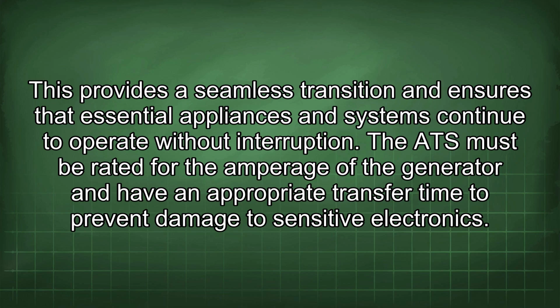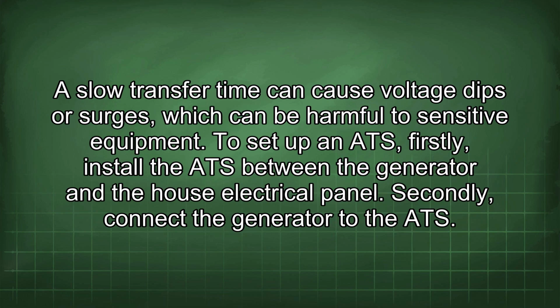The ATS must be rated for the amperage of the generator and have an appropriate transfer time to prevent damage to sensitive electronics. A slow transfer time can cause voltage dips or surges, which can be harmful to sensitive equipment.